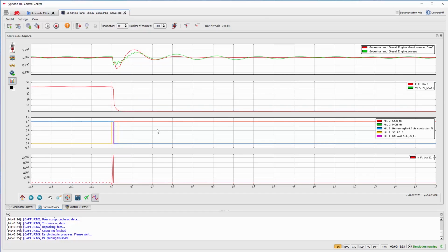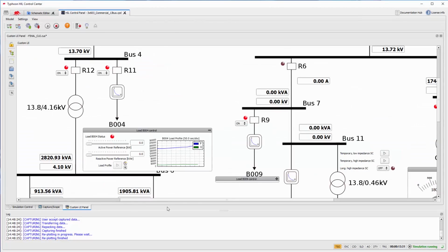Through this capture, we can see that the Gen 1 speed response is faster, but has higher amplitude oscillation. Now let us clear the Relay 6 register and allow it to reclose. Also, let us reconnect the DERs that tripped off. Our microgrid is back to its nominal operation.